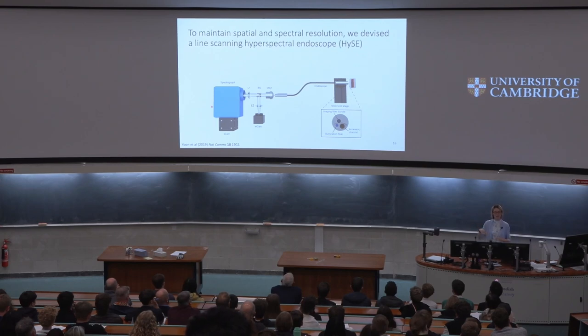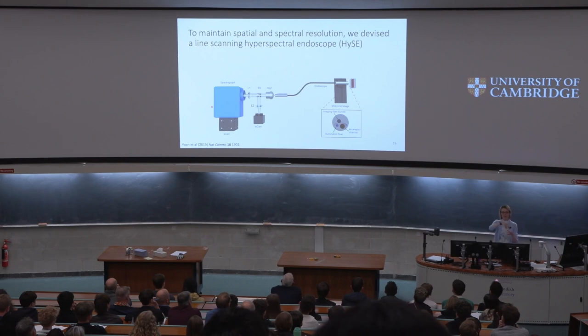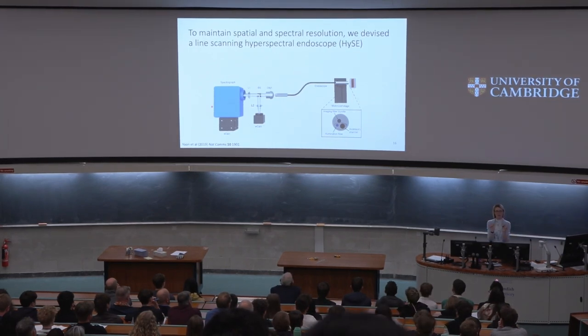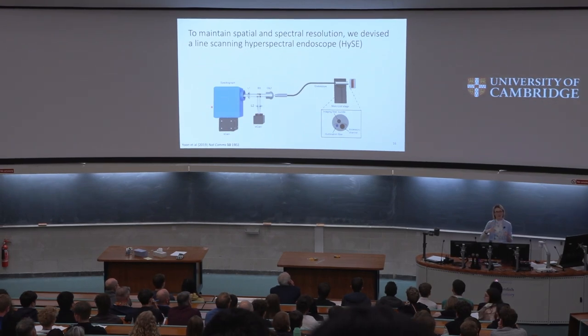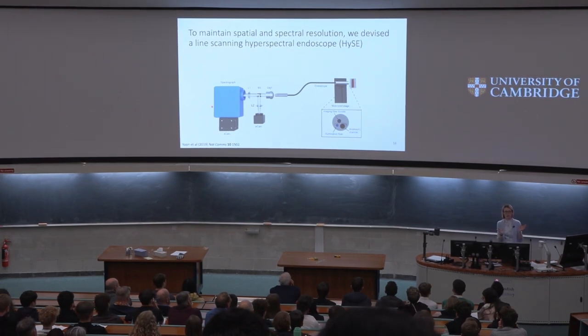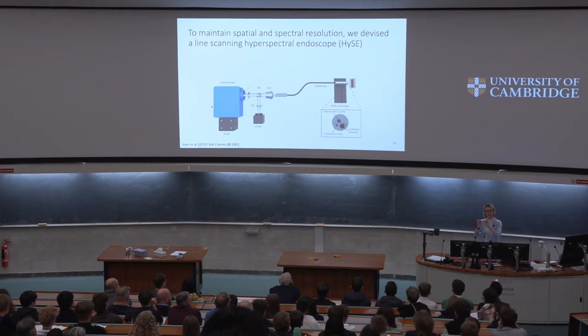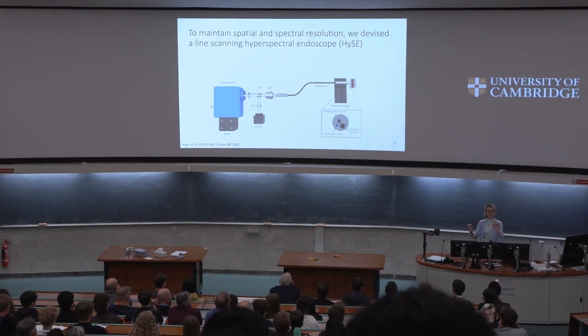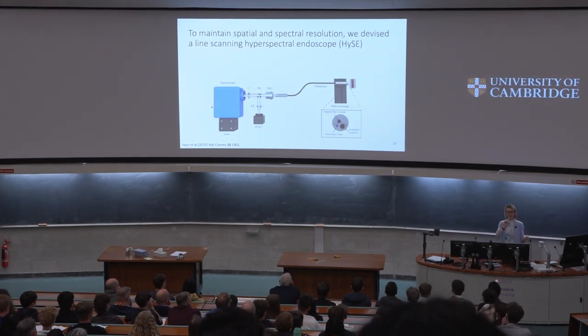A point scanning spectrometer takes a point of light, either focused through an objective or from a fiber optic, interrogates that specific region, and as it relays the light back, applies it to some dispersion optics, which might be as simple as a prism or more complex, such as a diffraction grating, and images onto a one-dimensional detector. So at any given point in space or time where I'm applying this point detector, I can get a single spectrum.